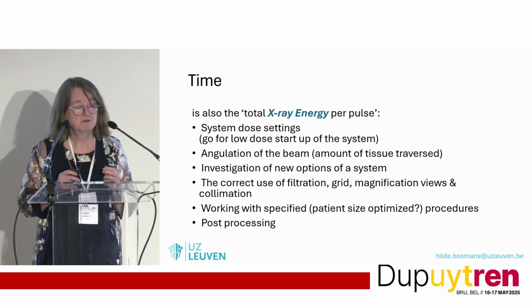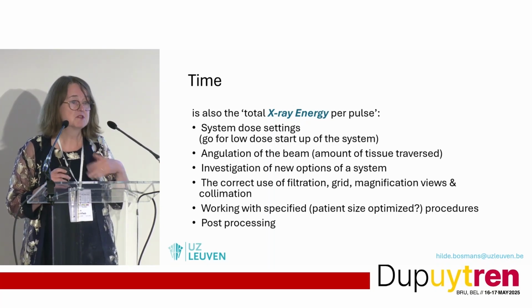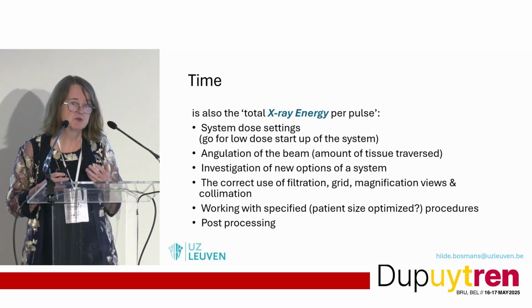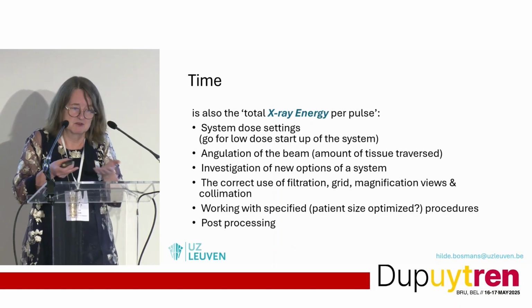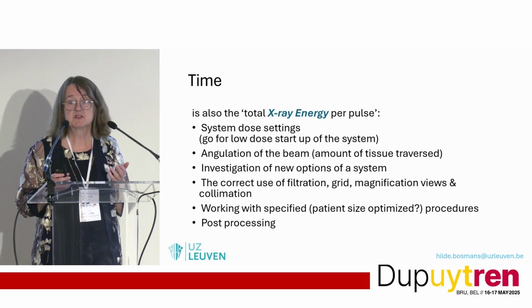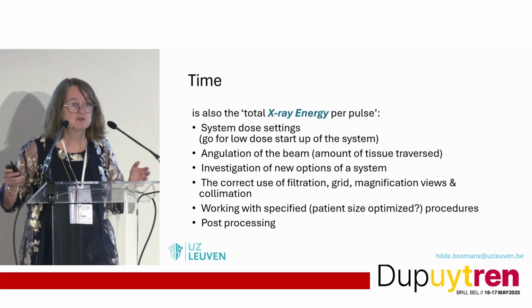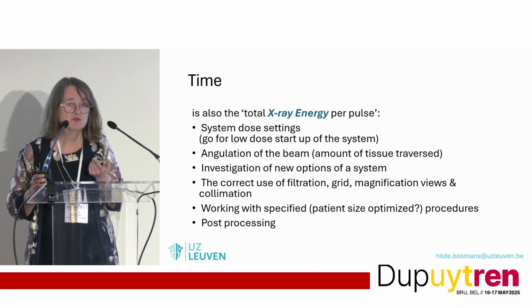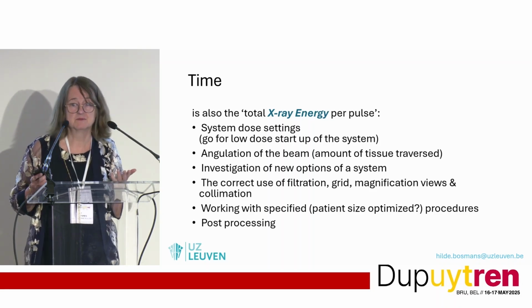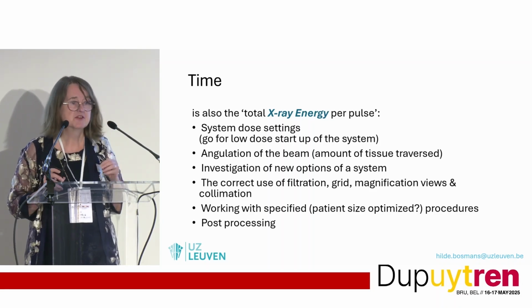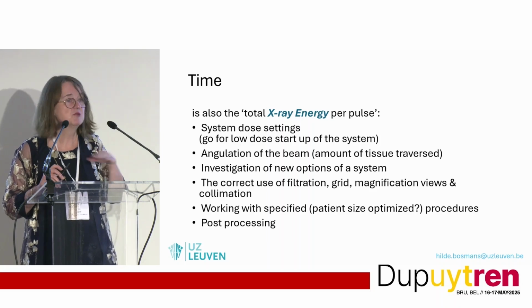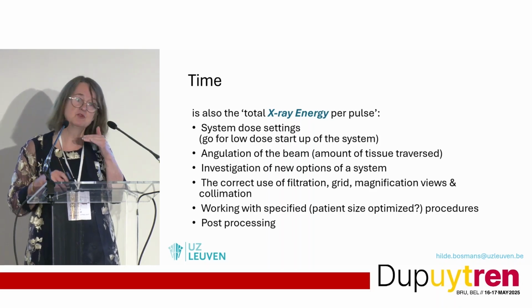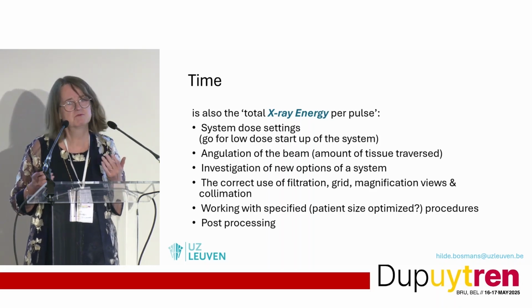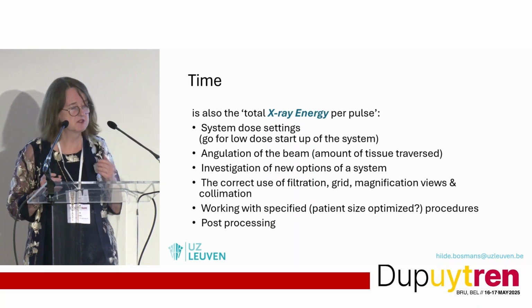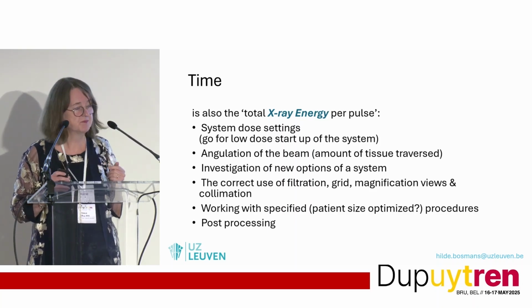And one good trick may be to set up your system such that the low dose mode is the routine thing when you start up the system, and that your personnel knows how to go to the higher mode if you need this. And not the other way around. Not thinking we start at a very good quality, and if the quality is too good, we're going to reduce the dose. No, the other way around is better. And that worked in our cath lab.